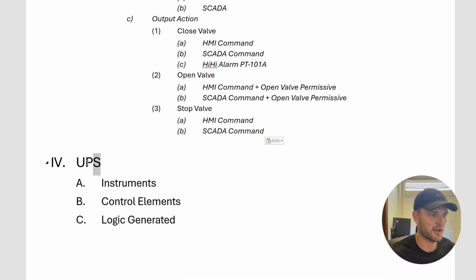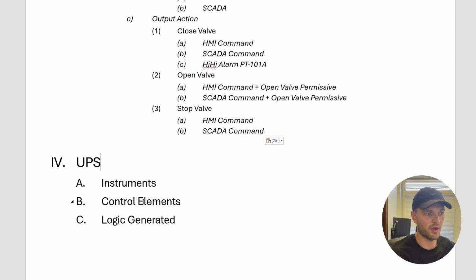As I mentioned earlier, we also maybe have another system, a UPS system, right? So this allows the UPS system to kind of be tested independently. There are some signals that will go over to our PLC, and we can include those under the instruments tab, maybe like a low DC alarm or high DC alarm or battery fail, right? And we can include those in here. Again, in software development, I may be butchering this term, but I think there's something called test driven development, where before you start developing anything, you think about what do you need to test in the end. That's what I use a control narrative for: what am I going to test in the end, document it, and then when I'm out in the field, make sure I sign off on all these items in this list.